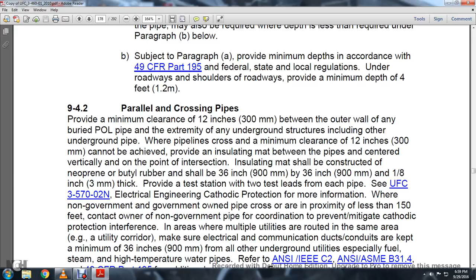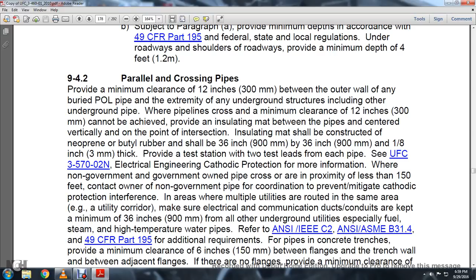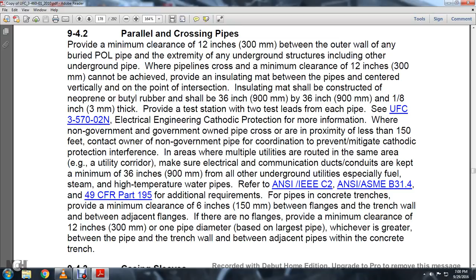For additional requirements for the pipes, see ANSI/IEEE C2, ASME B31.4, and Title 49 CFR Part 195. In concrete trenches, provide a minimum clearance of 6 inches between the flange and trench walls and between adjacent flanges. If there is no flange, provide a minimum clearance of 12 inches or one pipe diameter based on the largest pipe, whichever is greater, between the pipe and the trench wall and between adjacent pipes within the concrete trench.